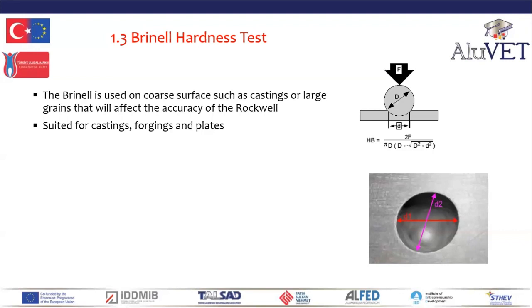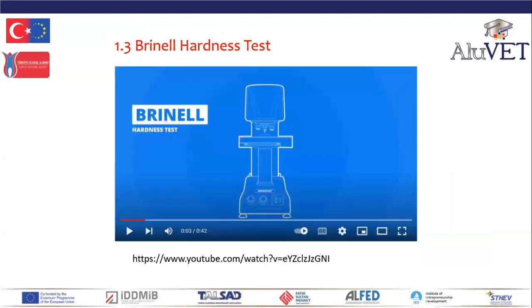Now, because the Brinell hardness test uses a large ball and a large diameter, it is very much a macro hardness test. So we can use it on castings, on hot rolled plate, on forgings. Now I have a short video on a Brinell hardness test here. Now this is quite an advanced tester, much more advanced than most people will use. So the process is automated, and also the microscope is built into the hardness tester, where older machines would use a separate standalone microscope.